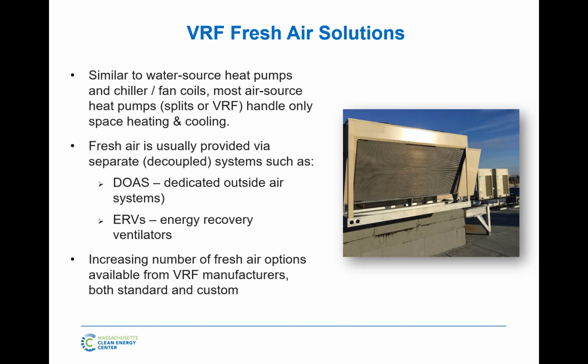The word DOAS is often used, dedicated outside air unit, as a decoupled system. So essentially, here's your VRF system, or here's your water source heat pump, your ground source heat pump, chiller, fan coil, whatever it might be. Here's a separate unit that's either on the roof or indoors, depending on the design, that's going to treat your outside air, your fresh air, and deliver it to the building.